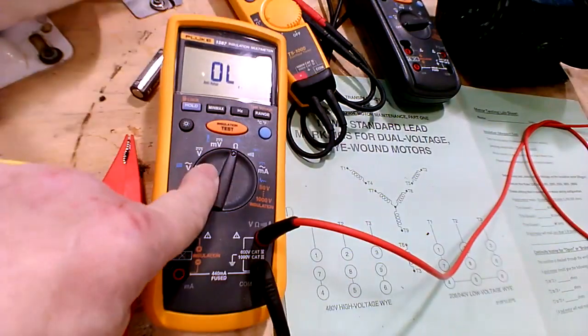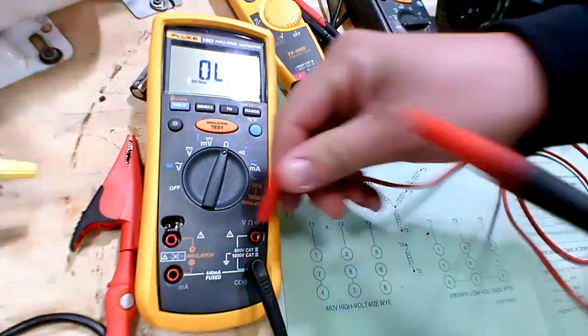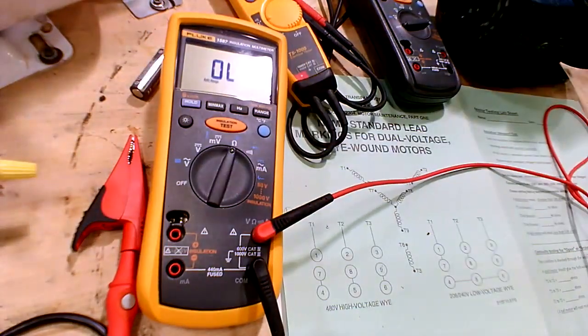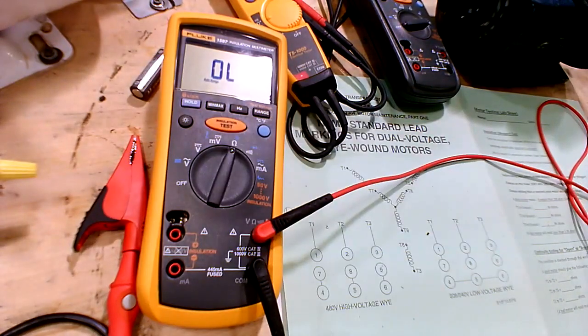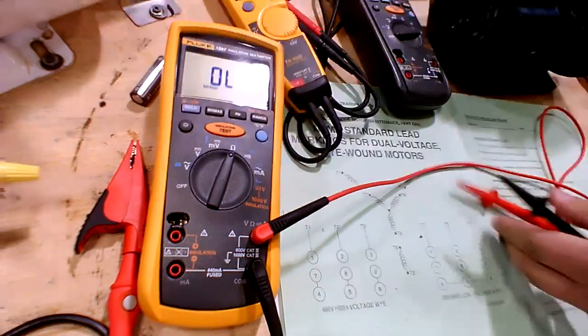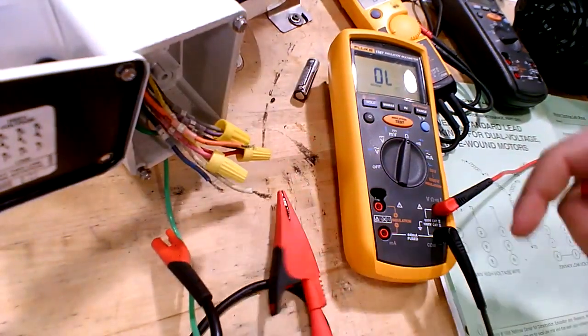You're going to switch over to these 2, and you go to ohms, and now touch the leads together. Make sure that it has a low resistance, and it does, 0.3 ohms. So that makes the test lead fine. Now put the clips on there and do the same. Come over here and check this one through it. This is a good meter.